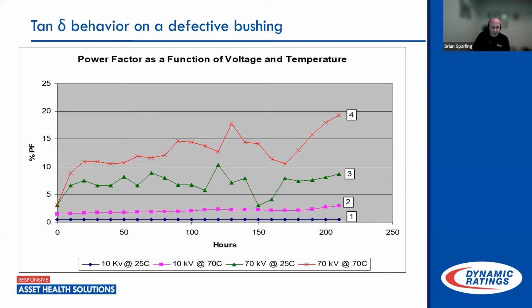And we know that dissipation factor is very sensitive to moisture and to voltage, to the point that we conducted an experiment quite some time ago on this defective 69 kV bushing. And what you see here is a plot of different conditions of testing the bushing. So in the blue plot across the bottom, trace number 1 shows the typical 10 kV at 25 degrees C corrected power factor test value, as you would do manually on a bushing on a transformer. And it shows good results, I would say, tested at 10 kV and 25 degrees C. Trace number 2, the one in pink, shows again a 10 kV measurement, but now the bushing temperature is at 70 degrees C. And you can see now that the dissipation factor has increased ever so slightly, and is indicative of a failing condition of a bushing.